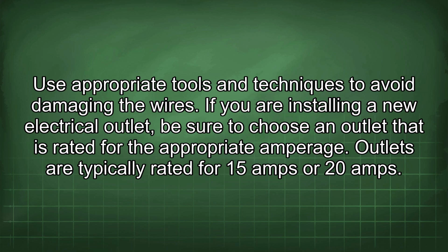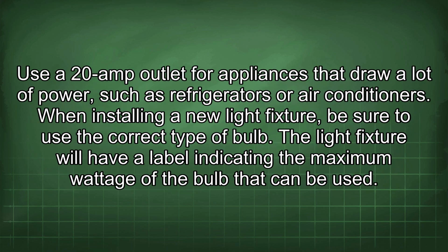If you are installing a new electrical outlet, be sure to choose an outlet that is rated for the appropriate amperage. Outlets are typically rated for 15 amps or 20 amps. Use a 20 amp outlet for appliances that draw a lot of power, such as refrigerators or air conditioners.